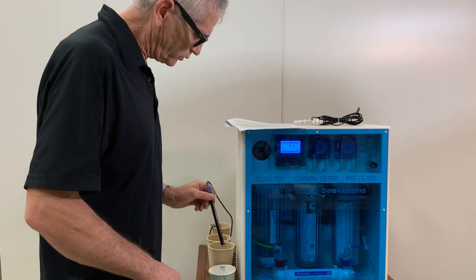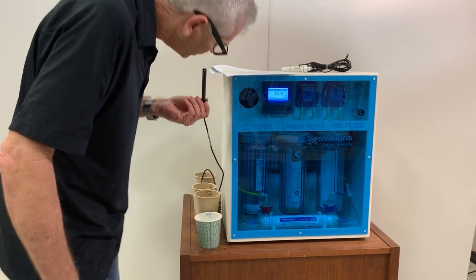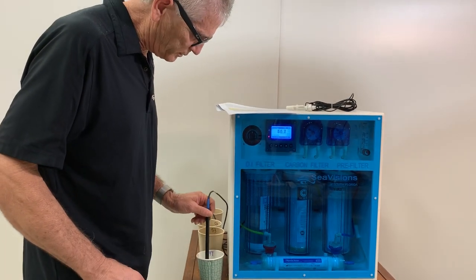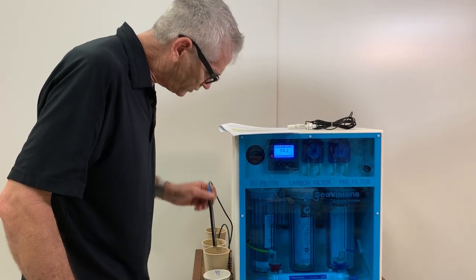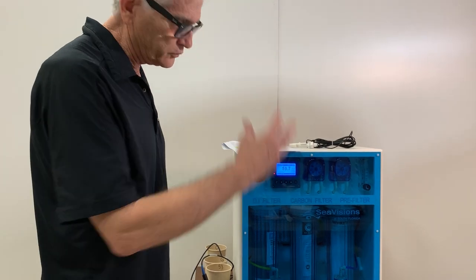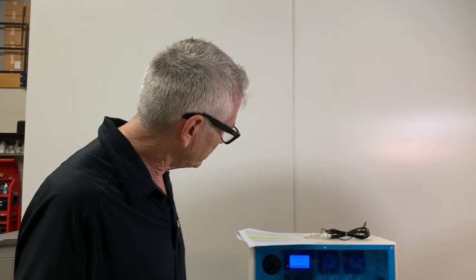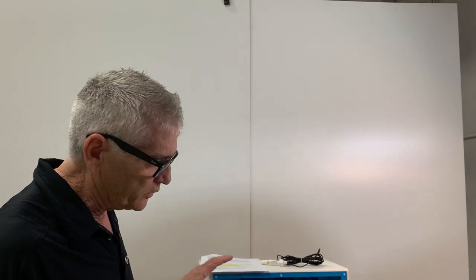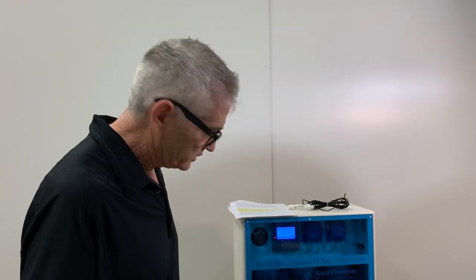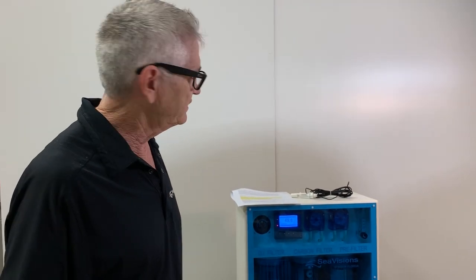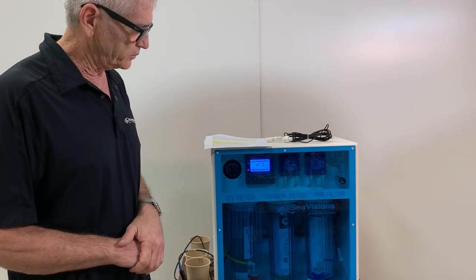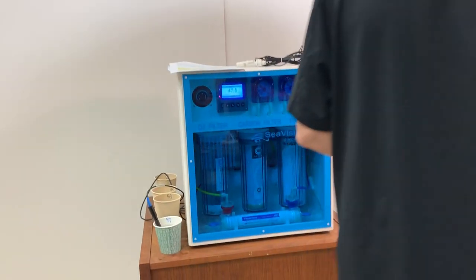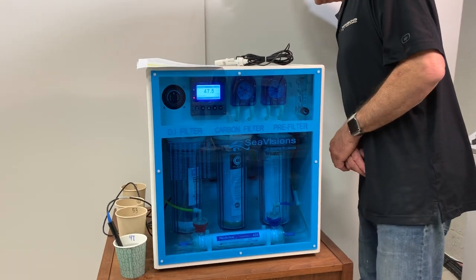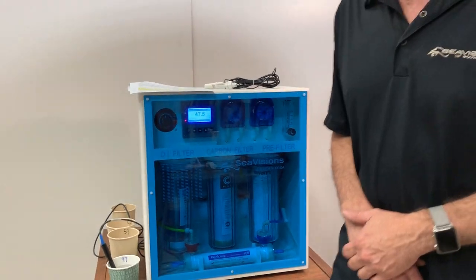I will have some DI water, I'll dip it in there many times, I'll blow on the probe, I'll put it back in the DI water, blow it on the probe, and boom, it usually goes right back to working correctly. If you find that it's erratic, change the probe. It's not that difficult. There's four screws on the back of the machine. You change the probe. So that's pretty much it.